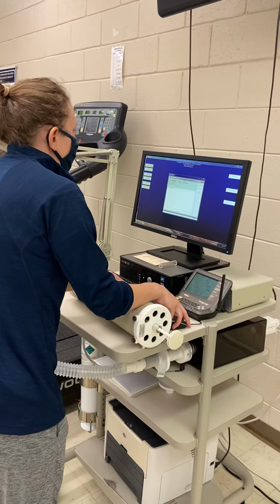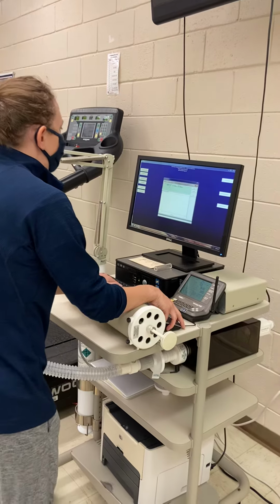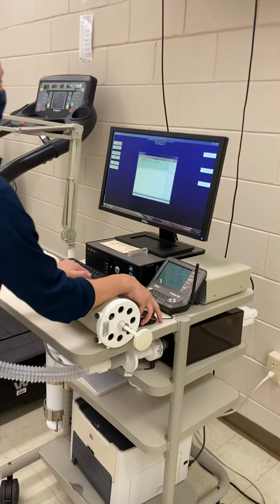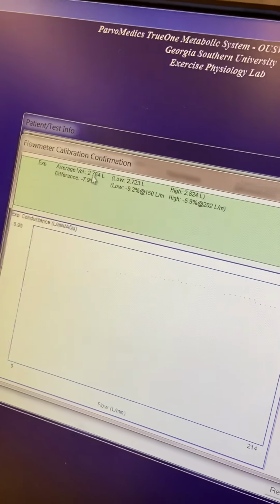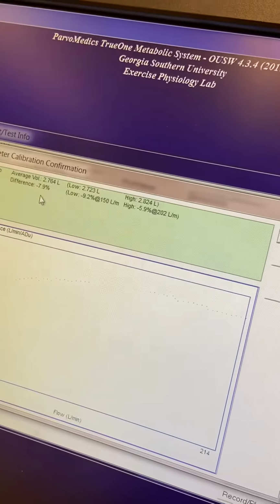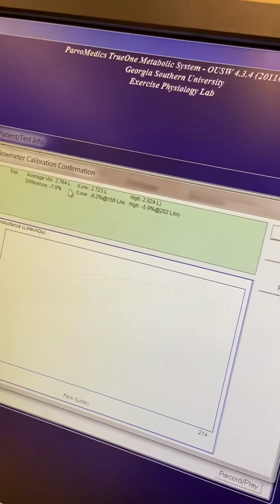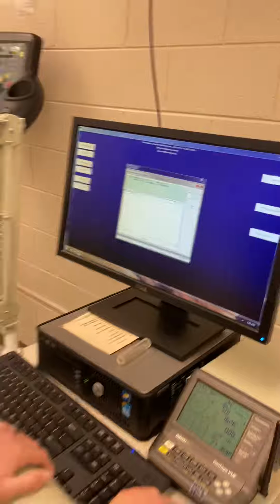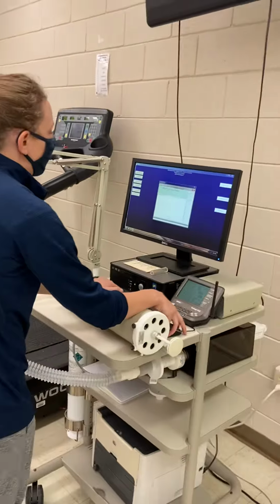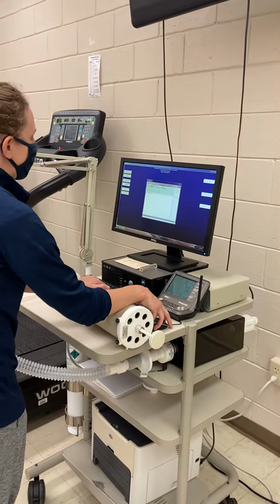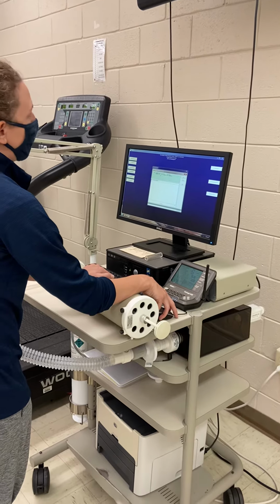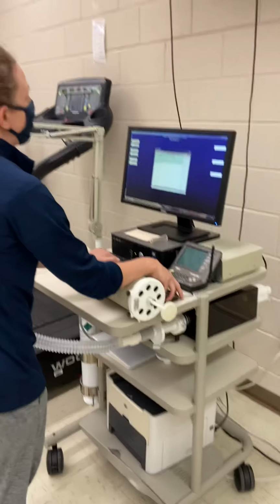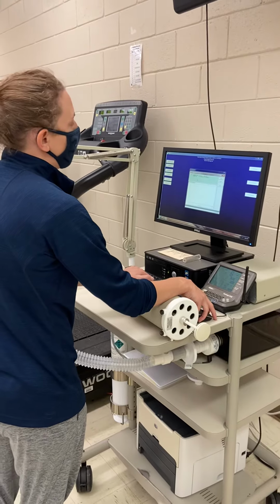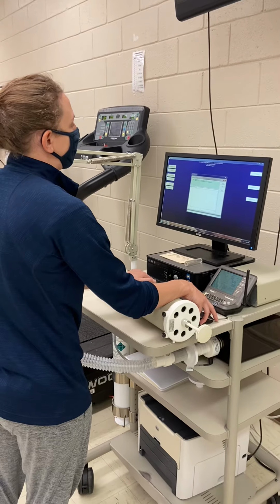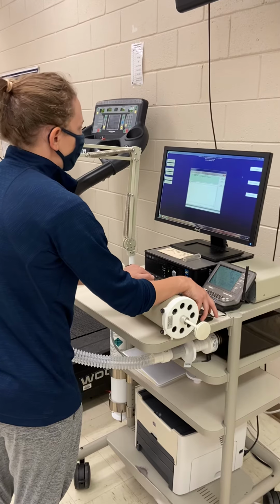Really want this to be within 5%. So the average volume that we're getting a reading now, if you look at this number, is 2.764. So we're potentially going to be running into an issue during this measure. So you'll see what happens shortly, because we want that to be close to 3 liters. Normally when I've measured this in the past, it's been like 3.02 up to 3.2. So usually it's more, not typically less. So we'll see what happens.